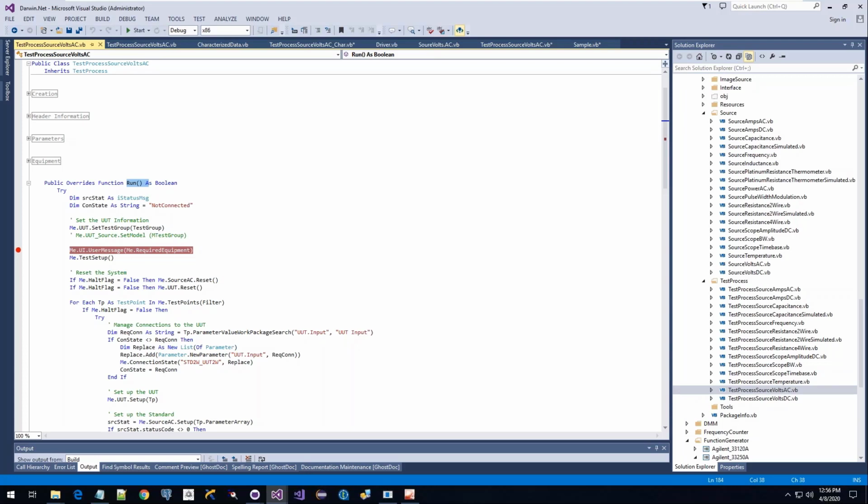So Jack, back to your question. Somebody could write a driver that would say, I'm going to look at my measurement uncertainty, and if I'm not 4-to-1, I'm going to skip that data point, or I'm going to ask the operator if he wants to do that. That's something that could be coded into the measurement processes. It's just that's not how we're coding our measurement processes. Okay, thank you.